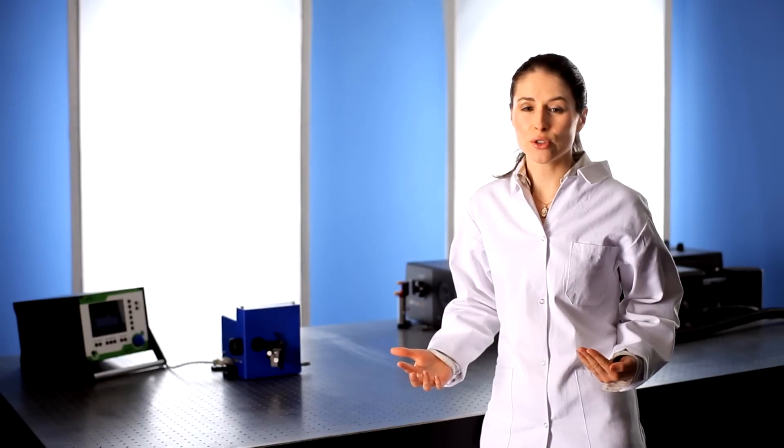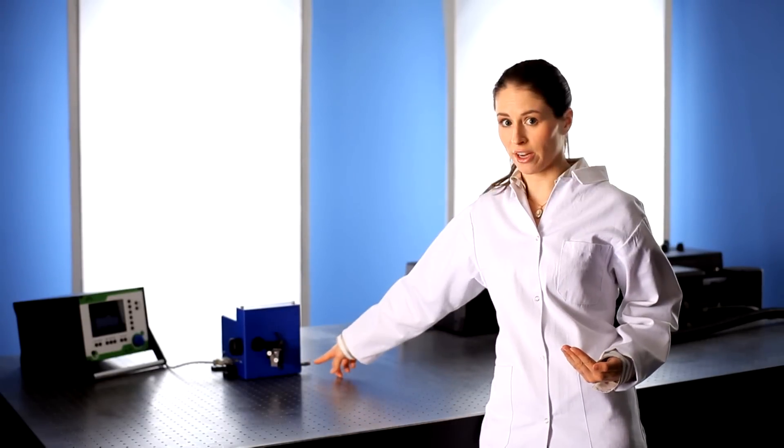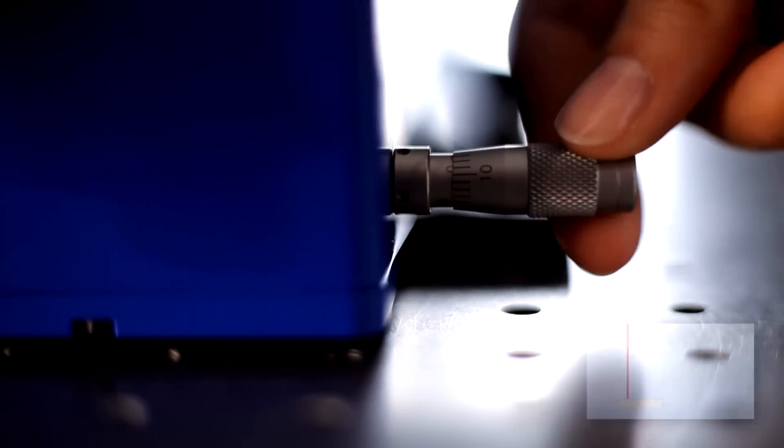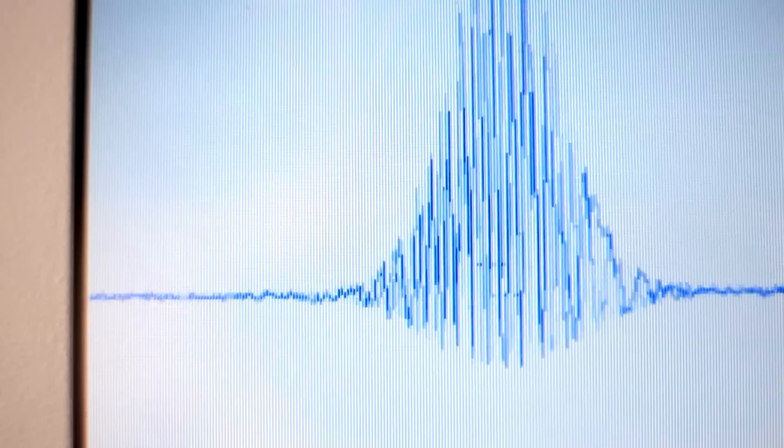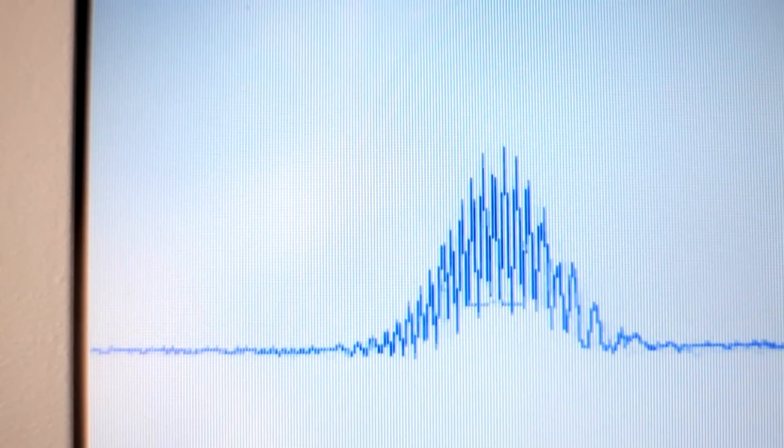And switching to non-collinear mode is easy. You can do it by turning a single micrometer screw, located here. As you turn the screw, you'll begin to see two beams in the crosshair, and your controller screen will start to show a clean measurement signal. Keep turning until the signal is perfectly smooth and background-free.